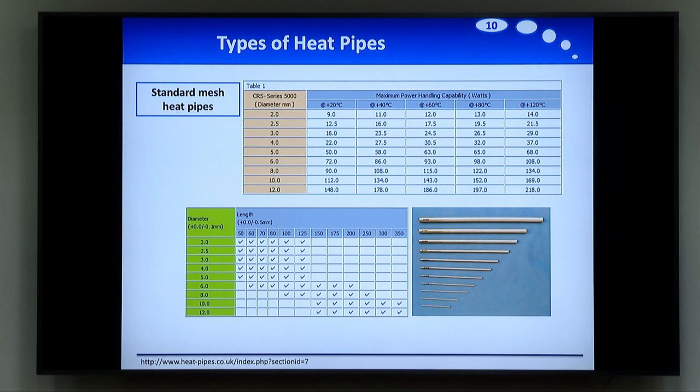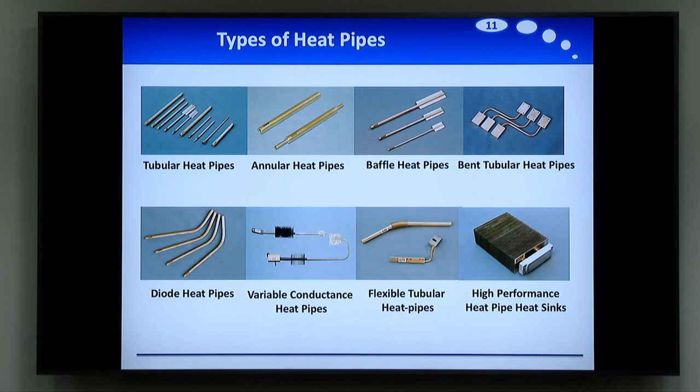For the types of heat pipes, as I said, there are really a lot. This can be found in the market — for example from company CRS, but there are many companies producing all these kinds of heat pipes. We have tubular heat pipes, annular heat pipes, baffled heat pipes, bent tubular heat pipes, heat pipe heat sinks, flexible tubular heat pipes, variable conductance heat pipes, and diode pipes. The diode pipes are quite interesting: in the diode pipe you have a kind of valve, so heat pipes are completely symmetric normally, but with a diode pipe it's not the case — there is one direction that works and the other direction still works but with very low performance. This is interesting if you want to be sure that heat is going only in one direction.